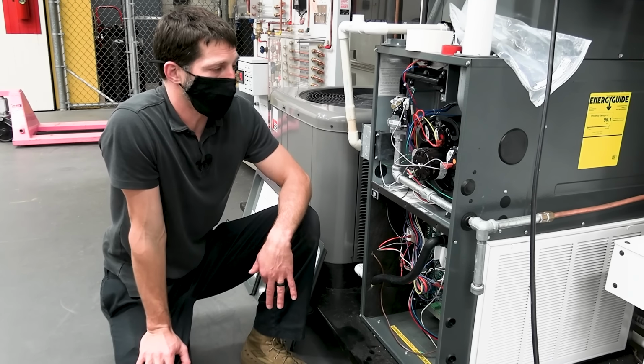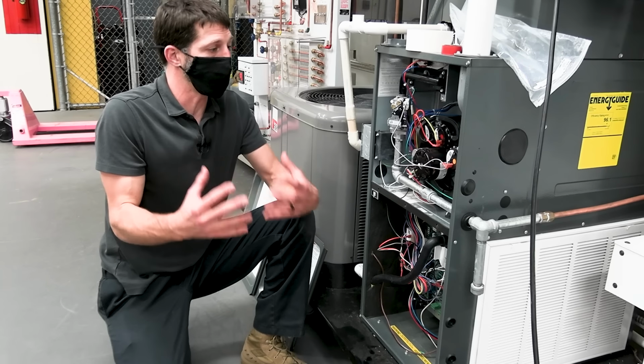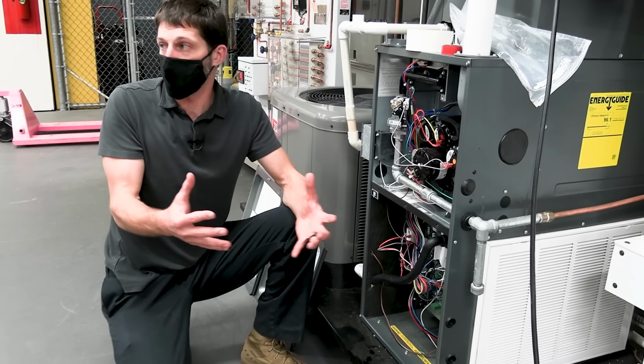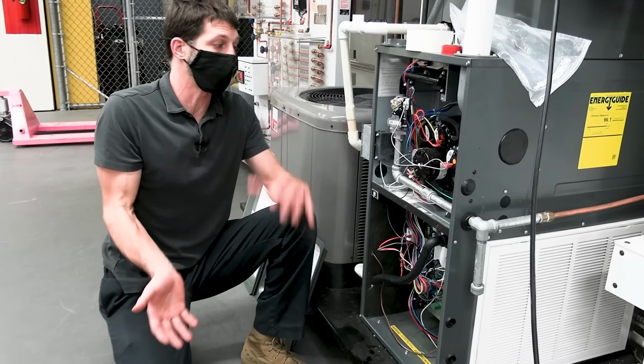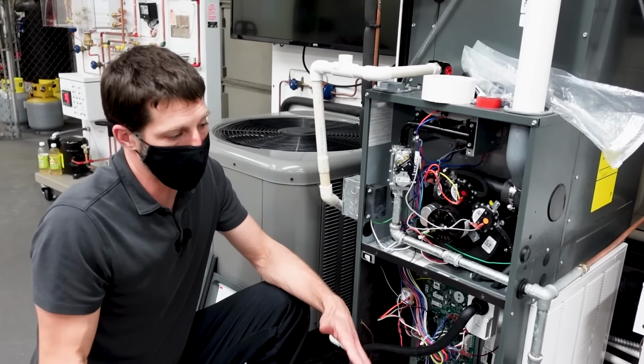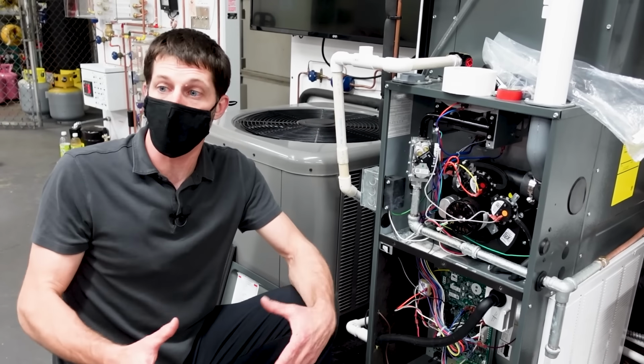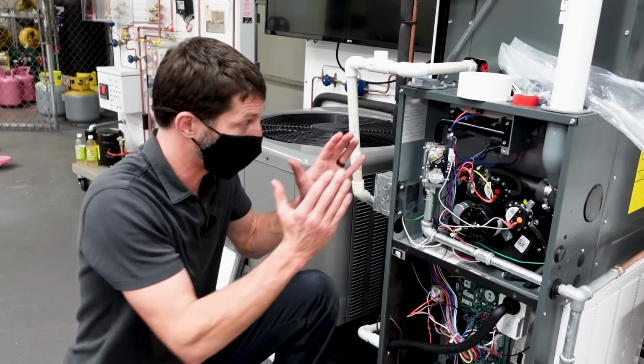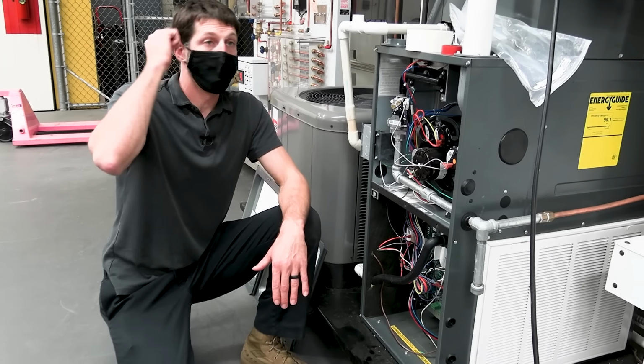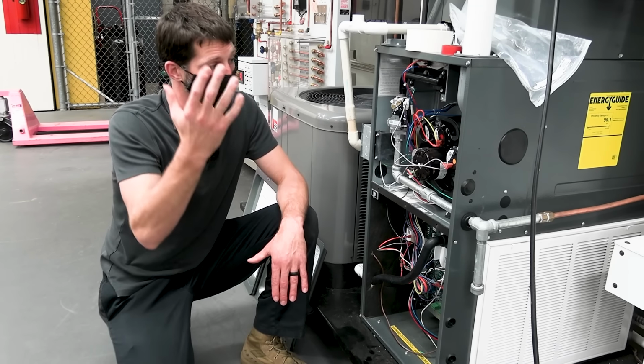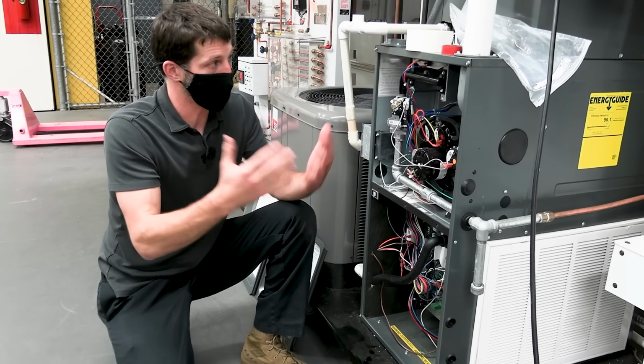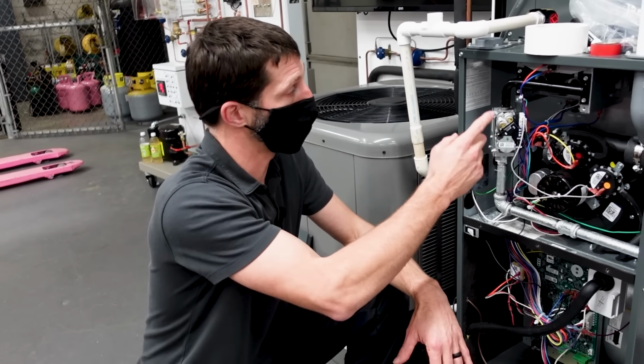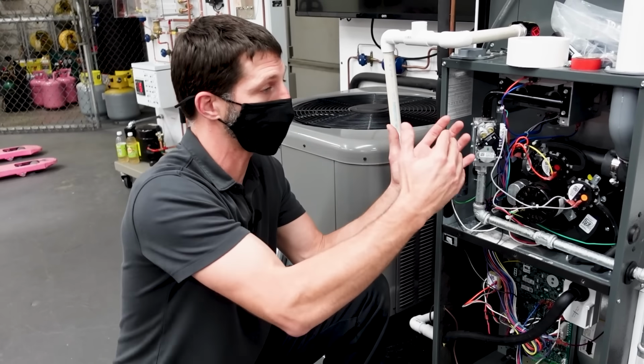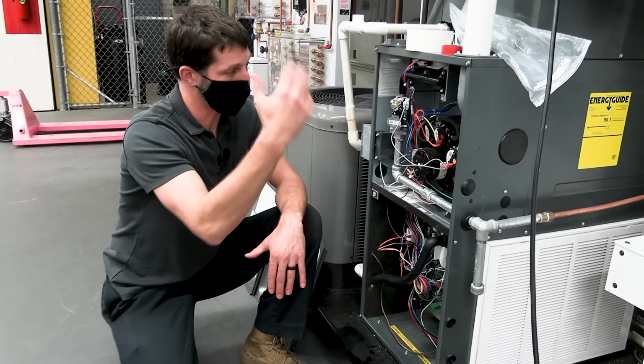But basically, you want to be able to give the customer confidence that you did find the crack in the heat exchanger, because there's a lot of people out there that want to sell a new furnace, and you don't want to be somebody that's guessing. You want to be able to try your best, if possible, to confirm that. And once again, if you're reading high levels of carbon monoxide at the supply registers, that's a pure indication, hey, you have carbon monoxide issues because the flame is burning improperly and it's getting into the conditioned air within the building.